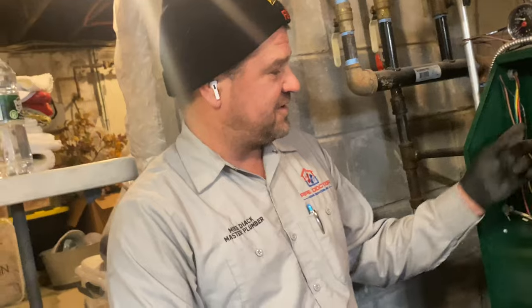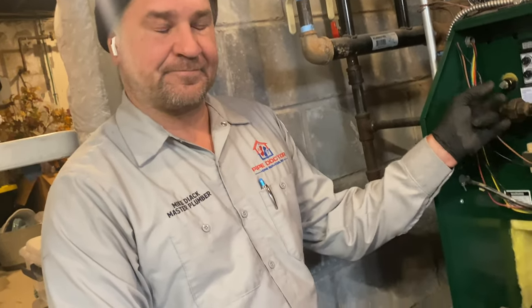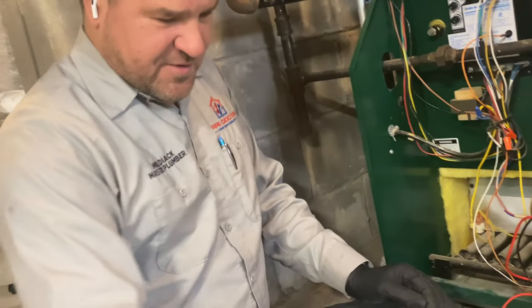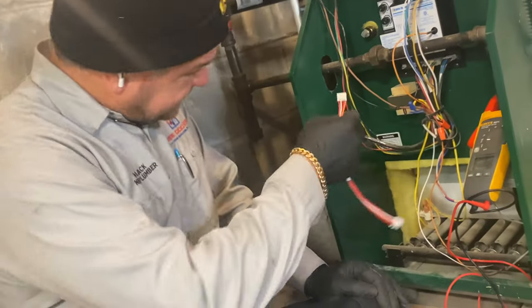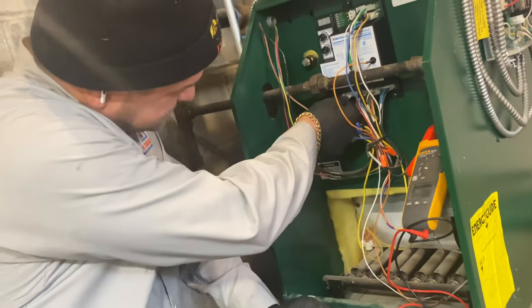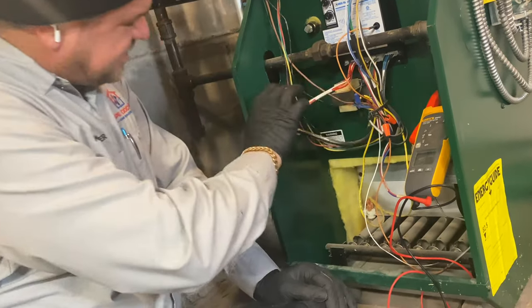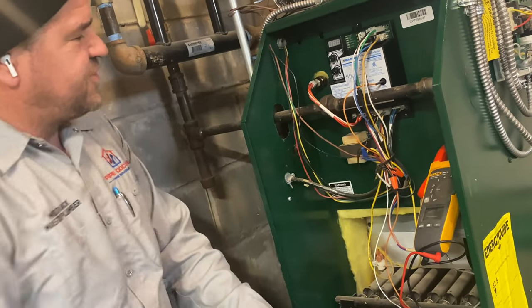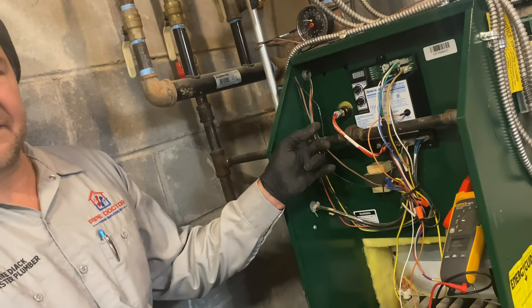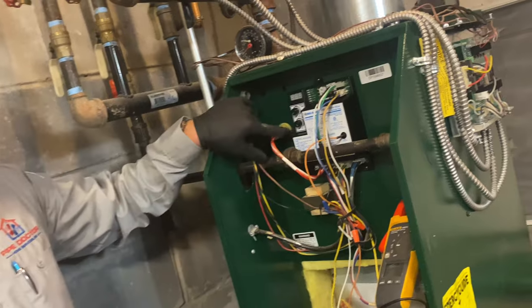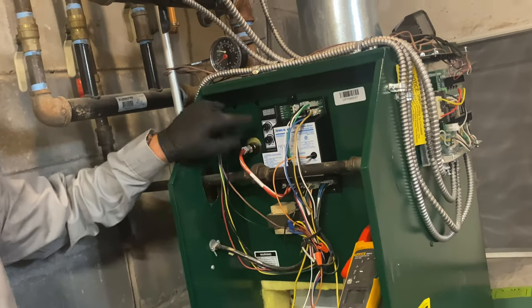Okay, the only thing we did not connect is the temperature probe, temperature sensor. For now, we're going to plug that back in, because to replace that we have to drain the boiler down. I want to see how this boiler behaves with the existing temperature sensor in there. We're not touching any of the sensors right now. Right now, the boiler temperature is factory.